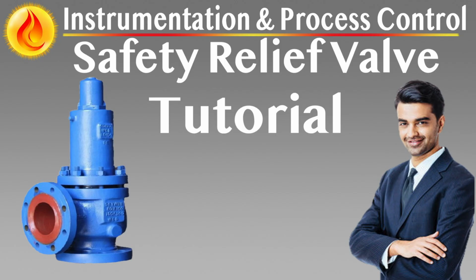Relief valves should conform to standard sizes as per API 526. Standardization across site should be maximized. Proposed valve sizes should be submitted for approval to reduce spares. Inlet and outlet flanges must be integral to the valve body unless otherwise approved. All flanges must meet ASME B16.5 standards. Flange ratings should correspond to the system pressure classification.